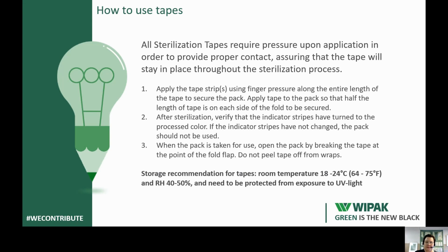It's also recommended that the tape is applied so that part of the tape is on the other side of the wrapped pack, and not covering the whole pack, because then it could break during the sterilization process. After sterilization, it needs to be verified that the indicators have changed to the processed color, which we as a manufacturer specify. If that's not happening, the wrapped items need to be sent for reprocessing, and the pack shouldn't be used.